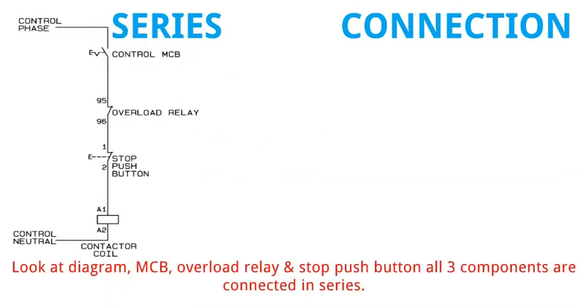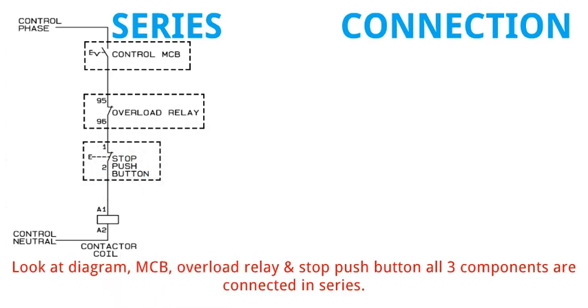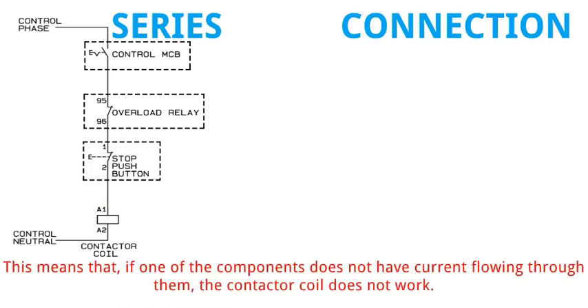Look at diagram. MCB, overload relay, and stop push button. All three components are connected in series. This means that if one of the components does not have current flowing through them, the contactor coil does not work.